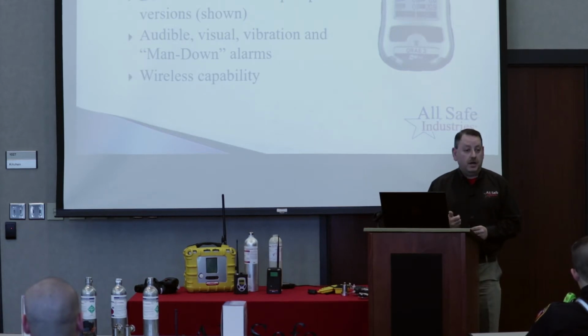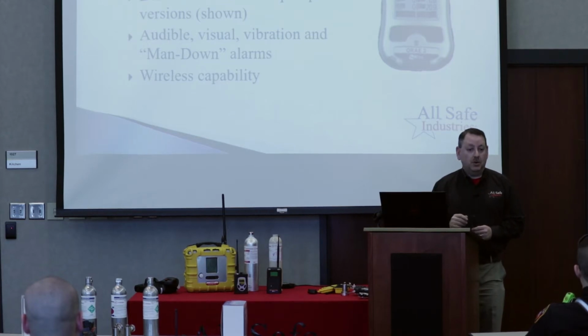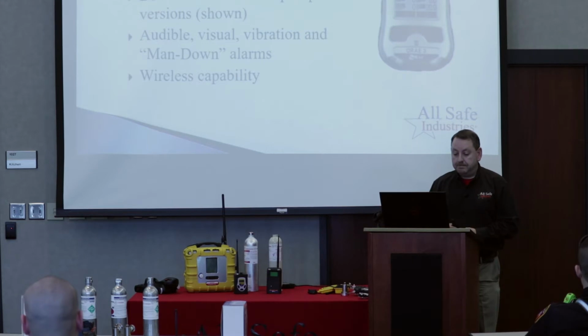And then this instrument also has audible alarms, visual alarms, vibration alarms, and what they call a man-down alarm. No offense, but it's just like the PASS device on your SCBAs. So if you have the man-down alarm turned on either of your instruments and you sit still too long, it's going to go into a pre-alarm to say, are you okay? It really says that on screen, are you okay? And if you don't move the instrument or acknowledge by pressing a button, it goes into what we call super alarm. All the alarms will go off to alert your coworkers that someone's down, and that way we can get to them. That's very useful in an industrial setting where oftentimes a maintenance guy will go off in part of the plant by himself. I'm pretty sure you guys are always buddy system, which is the best way to do it. And this one also has wireless capability, so we could do wireless 4-gas meters.